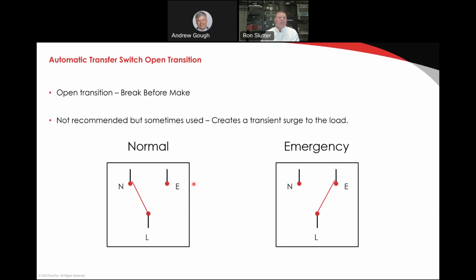When it becomes an issue is when we retransfer from emergency to normal. Because in that situation, we'll still have an emergency generator up and running, the normal utility source has returned and has been verified to be acceptable and available. So now we have two sources available. When this transfers back to the normal source, you will get a transient to your downstream loads. Okay, so this is not the best situation.